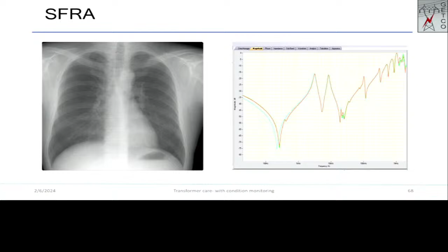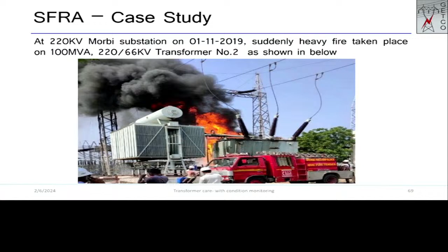So this is another use of tan delta. If we take the tip up test, okay, then if the graph is found flat, it is very good. If the slope is uniform, then good. If there is a difference in slope, then there is a chance of PD. And if there is a negative slope, please remove the bushing or transformer immediately. Clear? Okay. Now, one case study of SFRA I want to explain, not going into detail, but going directly to this.